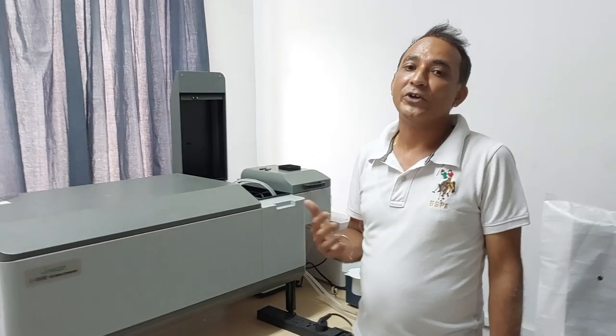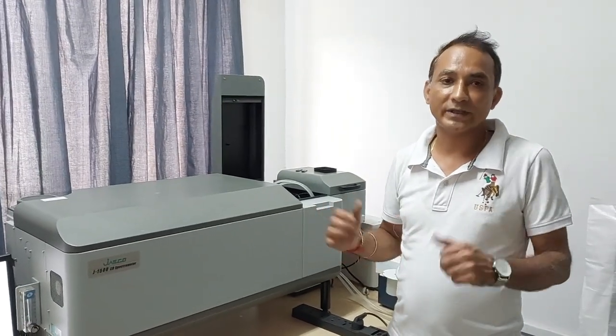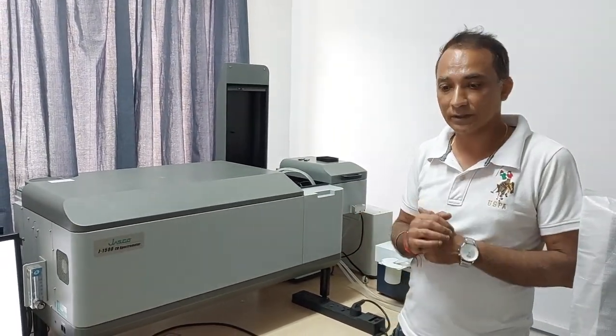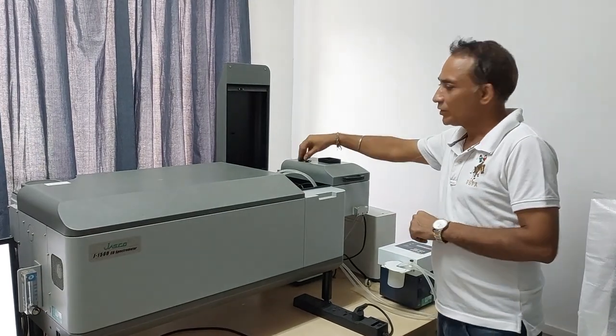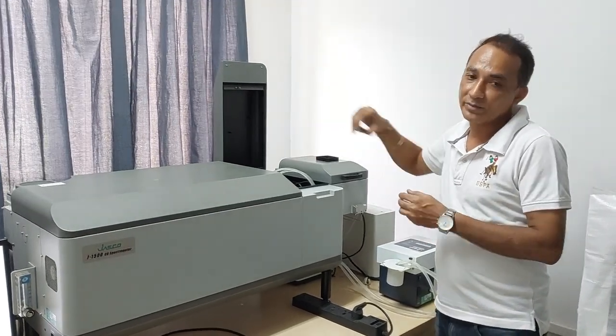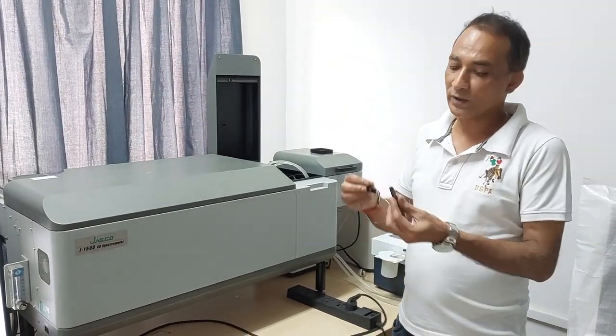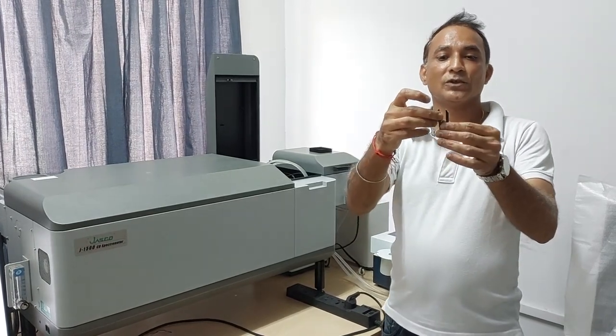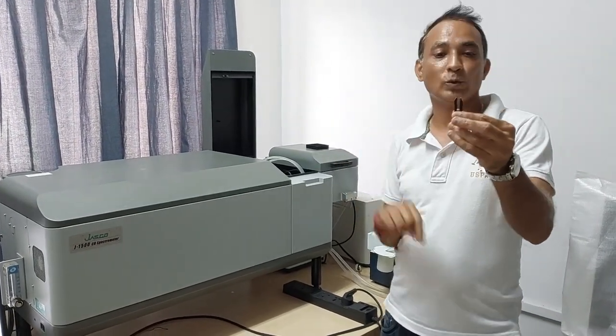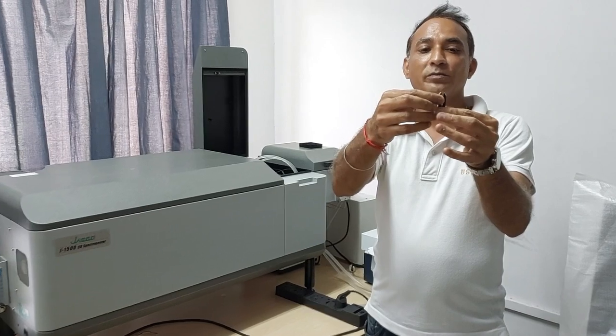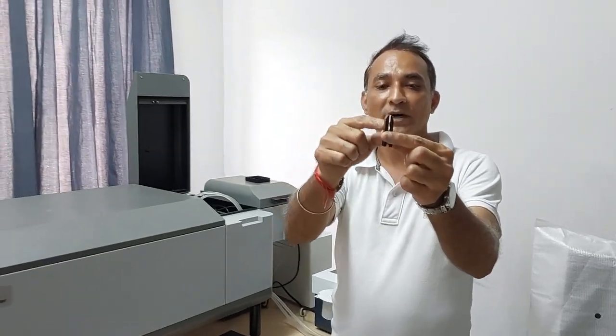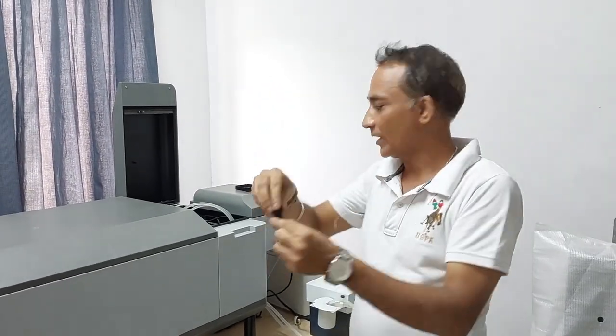A 1 centimeter path length cuvette is generally used for near UV CD, which is weak in intensity. But for far UV CD, you typically use a 1 millimeter path length cell. So you have these two adapters, you place them in the cuvette chamber, and you simply sandwich your 1 millimeter path length quartz cuvette between them and put it here.